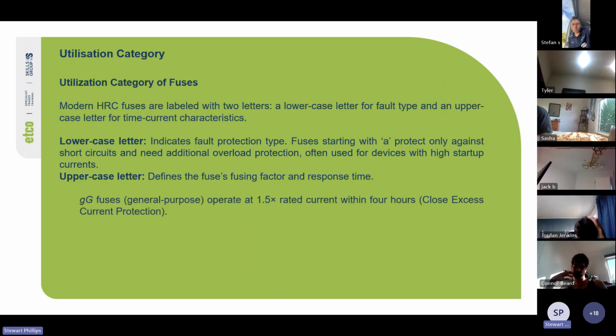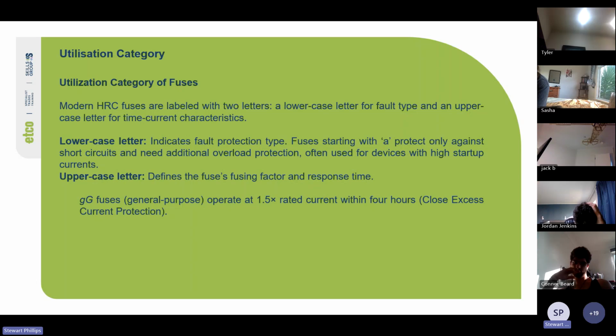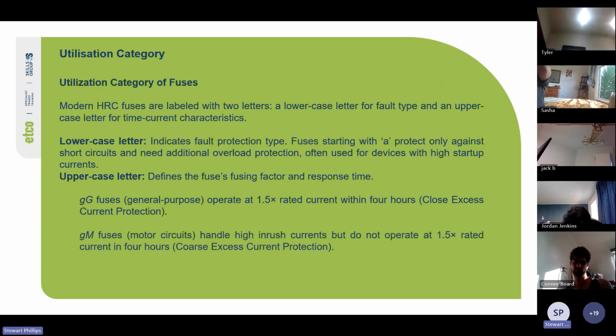So gG fuses, general purpose, operate at 1.5 times rated current within 4 hours. So close excess current protection. Whereas gM fuses, motor circuits, handle high inrush currents, but do not operate at 1.5 times the rated current in 4 hours. So it's coarse excess current protection. Whenever we talk about close or coarse excess current protection, we're always talking about 1.5 times the rated current and whether it's within or not within 4 hours.